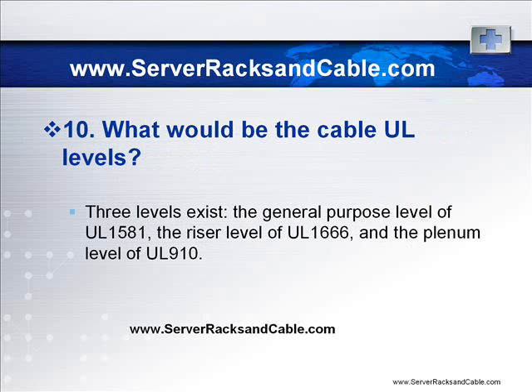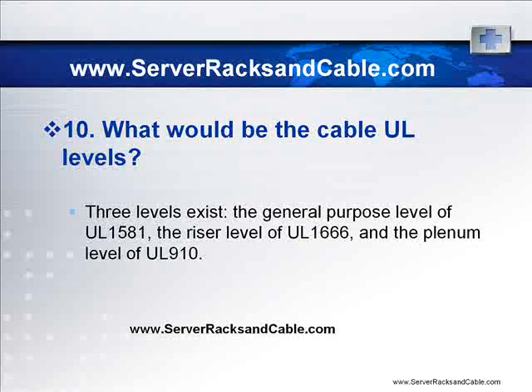What would be the cable UL levels? Three levels exist: the general purpose level UL-1581, the riser level of UL-1666, and the plenum level of UL-910. All these numbers are safety and fire rated.